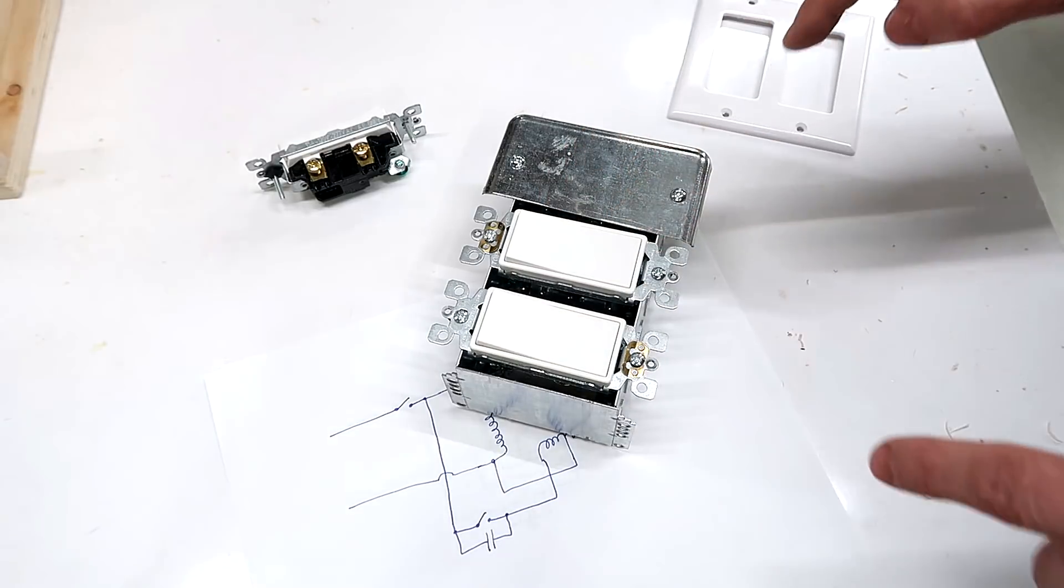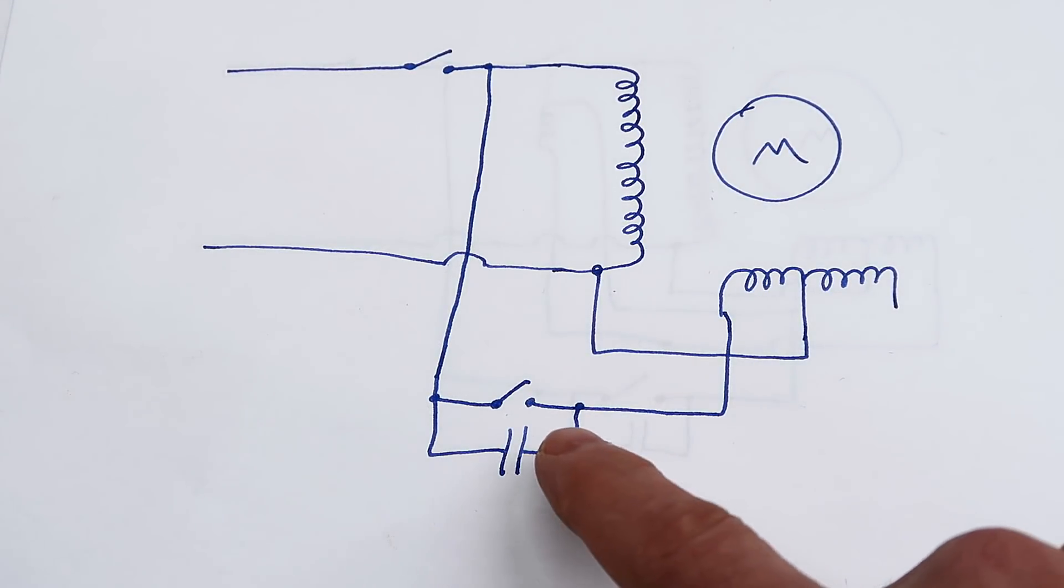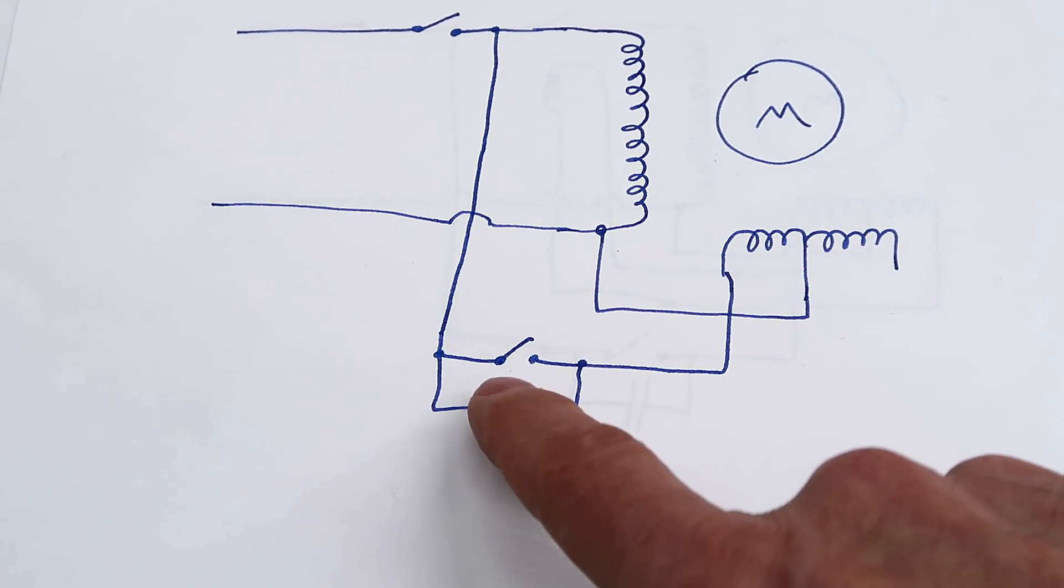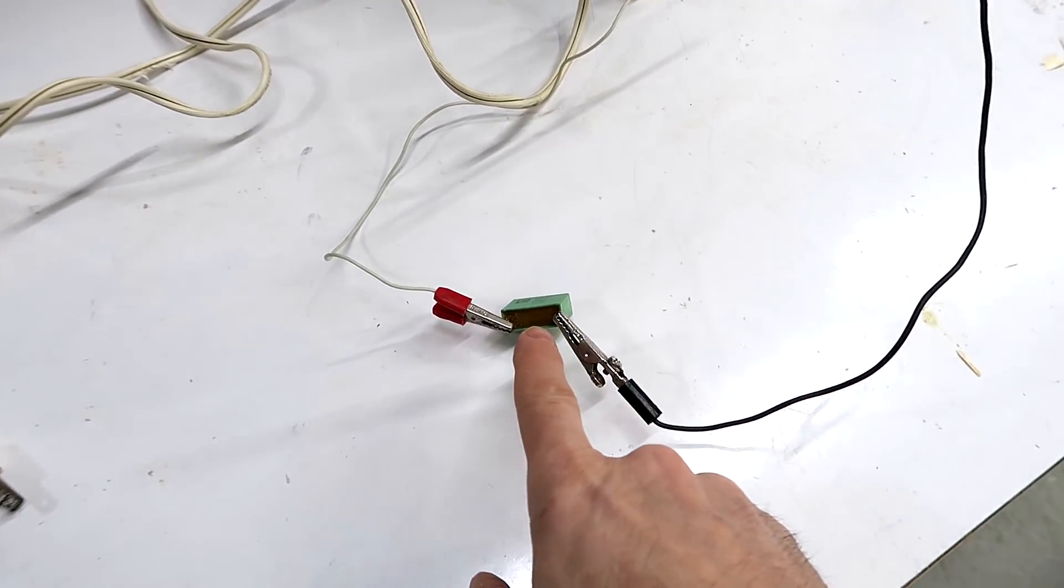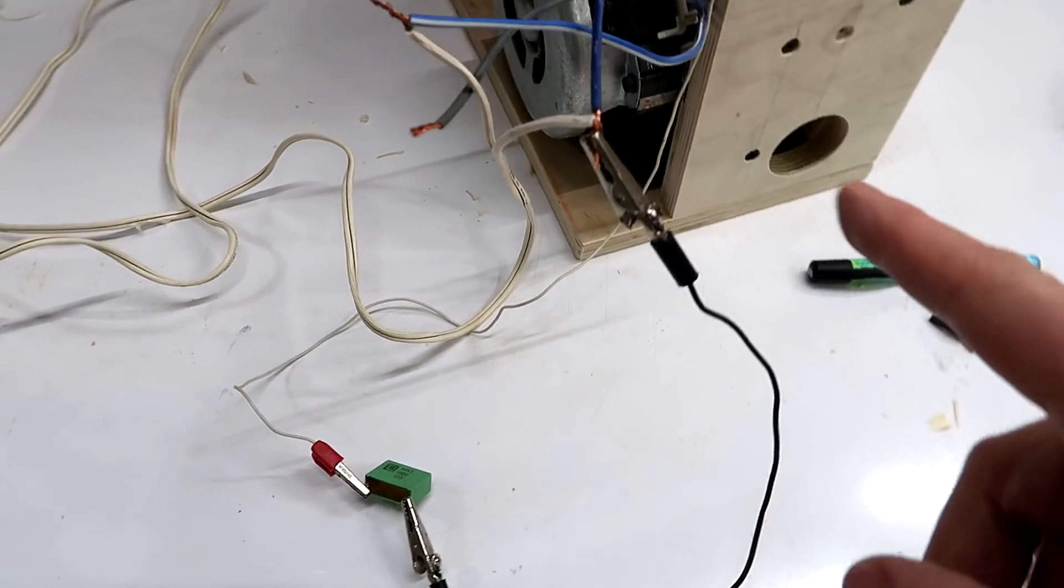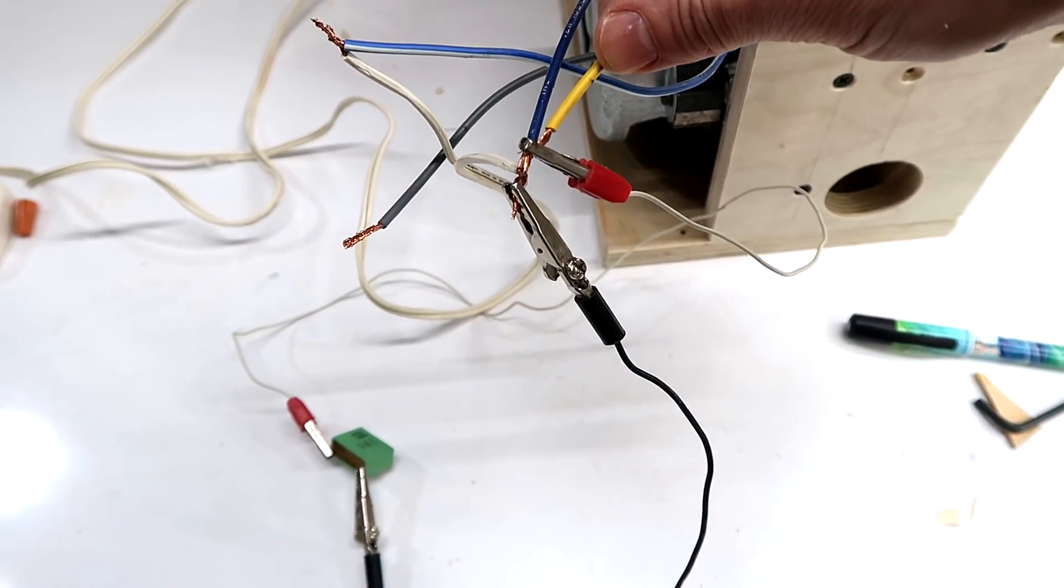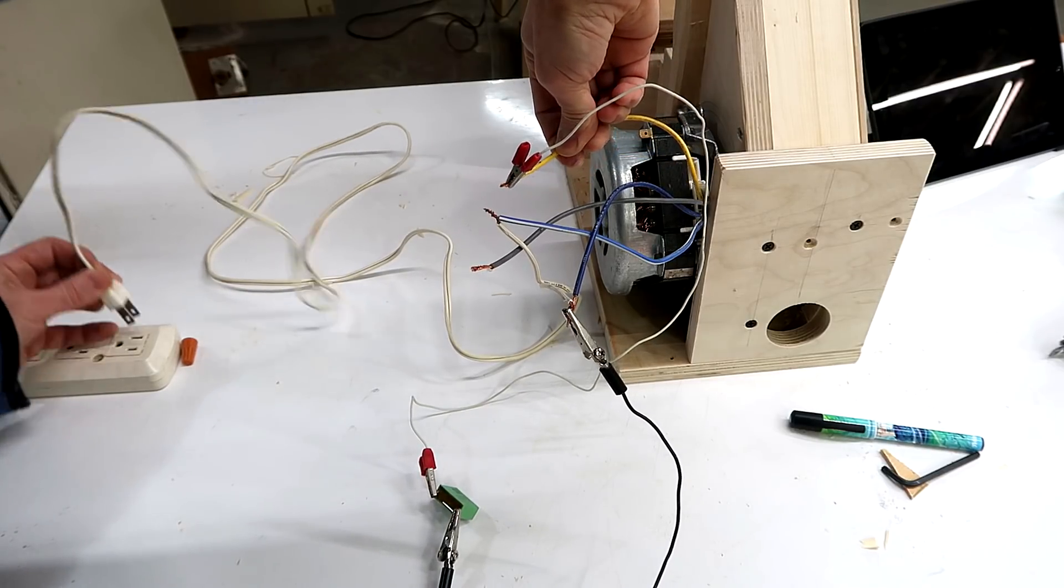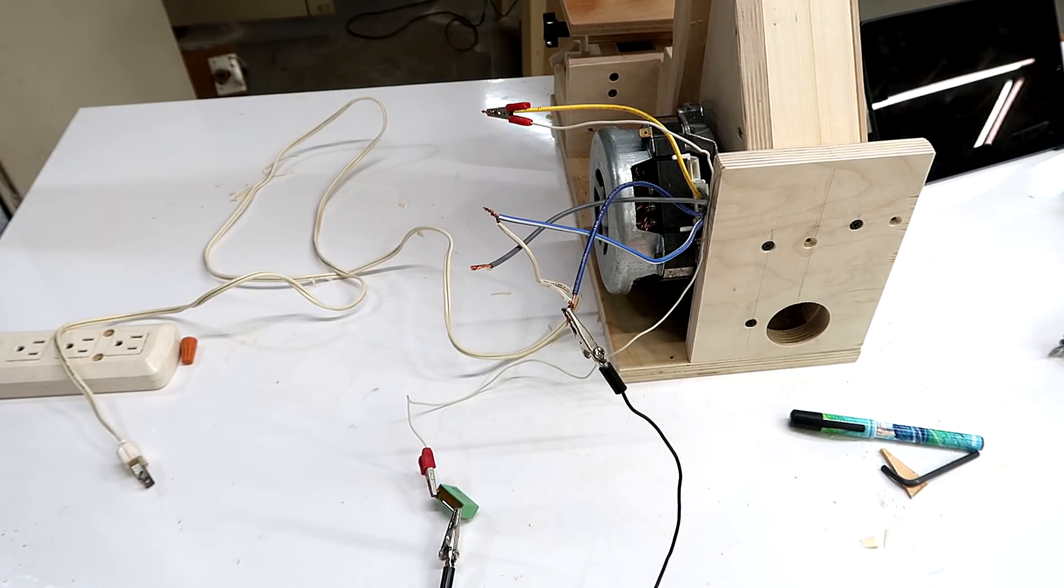Now you may have noticed when I disengaged the starter coil that made quite a spark. And if I put a capacitor in parallel to that, that will cut down on the spark quite a bit, which will make the switch last a lot longer. So I've got a 0.47 microfarad 400 volt AC capacitor in parallel with the contact that I need to close here. So that was almost no spark.